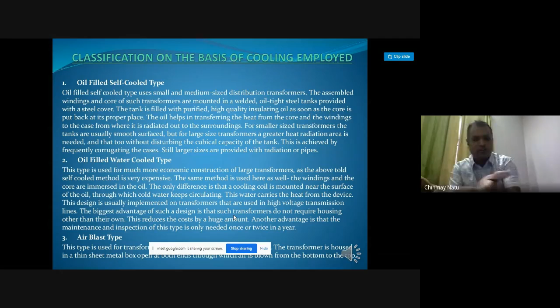The first type, oil-filled self-cooled, works like this: when there is a high voltage transmitting transformer, they submerge the whole coil and stepping assembly in oil, which provides cooling for the transformer against overheating. Because when there is high voltage, it creates a huge magnetic field, which causes eddy current and hysteresis losses. These cause the transformer to heat up, and if it gets too heated we lose the efficiency of the transformer. So this cooling system is widely used to cool the transformer.